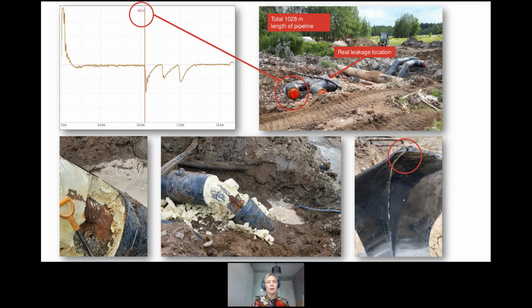That was dug up, first with a small window where we could see that the insulation was obviously completely wet. We found a crack in the casing pipe. The outside water had gone into the insulation. A severe corrosion had started happening. And if this had not been noticed, in a couple of years the main pipe would also have broken. So this is a great example of how leakages can be prevented, not only noticed when they happen.